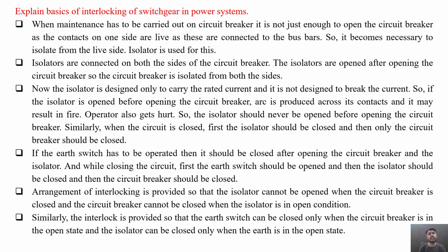Now the isolator is designed only to carry the rated current, and it is not designed to break the fault current. So if the isolator is opened before the opening of the circuit breaker, an arc is produced across its contacts and it may result in fire. The operator also gets hurt. So the isolator should never be opened before opening the circuit breaker.